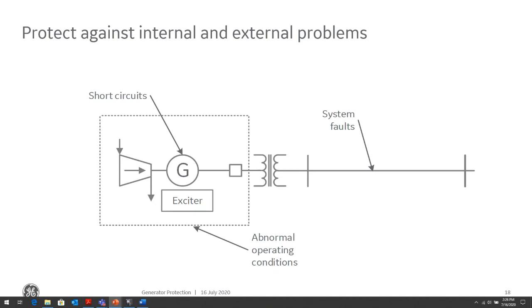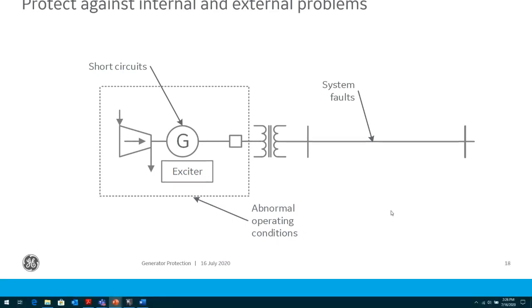These abnormal conditions are not just short circuits. When we talk about abnormal conditions, these are the internal abnormal conditions: overexcitation, abnormal frequency operation, reverse power, breaker failure, inadvertent energization of the generator, and a breaker pole flashover. Some of the external non-short circuit conditions can be loss of sync during a power system disturbance and an open phase out in our power system, and so we need to protect our generator from all of these conditions.